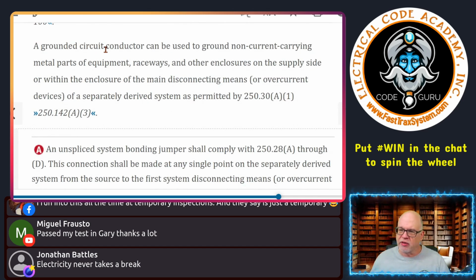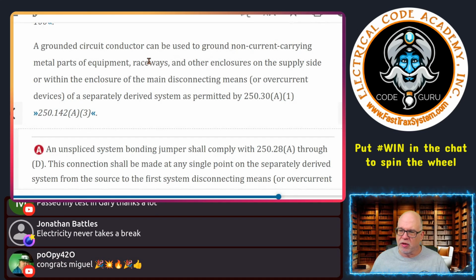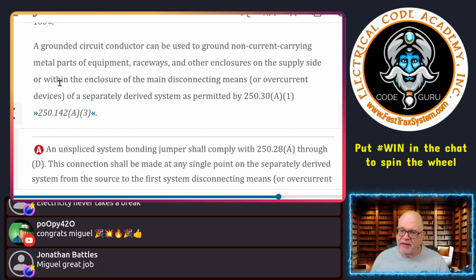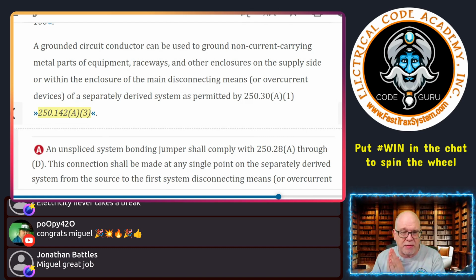A grounded circuit conductor can be used to ground non-current-carrying metal parts of equipment, raceways, and other enclosures on the supply side, or within the enclosure of a main disconnecting means or overcurrent devices of a separately derived system. That's where we typically would see our system bonding jumper, okay? So we have some allowances there in 250.30(A)(1). And we also get the allowance to use the grounded conductor to bond things on the supply side. If you're not familiar with that, for goodness' sake, go watch my video on how to do supply side bonding, because we very commonly use the neutral, which is probably more properly termed the grounded conductor, because we know all neutrals are grounded, but not all grounded conductors are neutral.